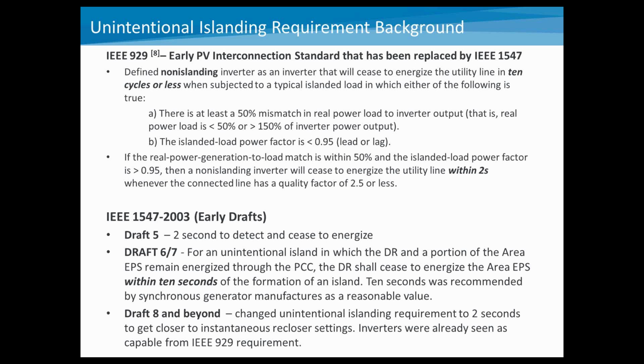So one of the things was a 10-cycle or less disconnection, and that's a really fast disconnection time, but it's also, as you can see from the requirements, for when the power mismatch is pretty great. And then if the power mismatch is within a certain nominal level, it's within 2 seconds. So that 2 seconds is kind of carried over from early PV interconnection standards.